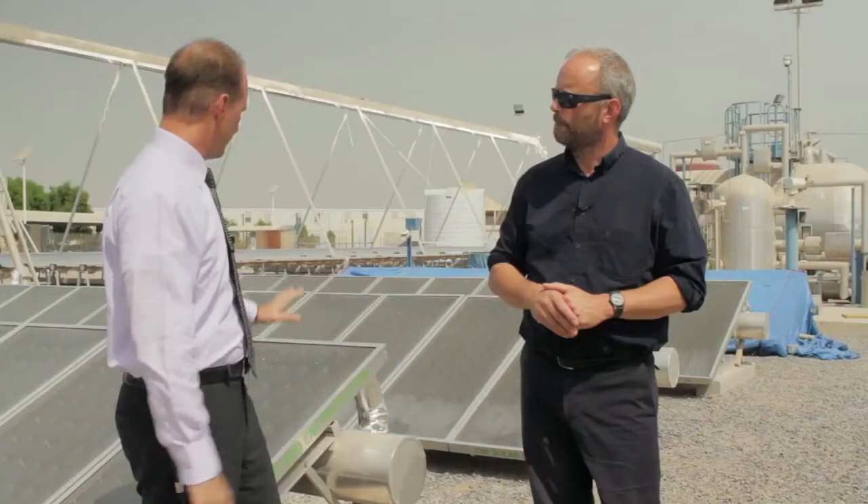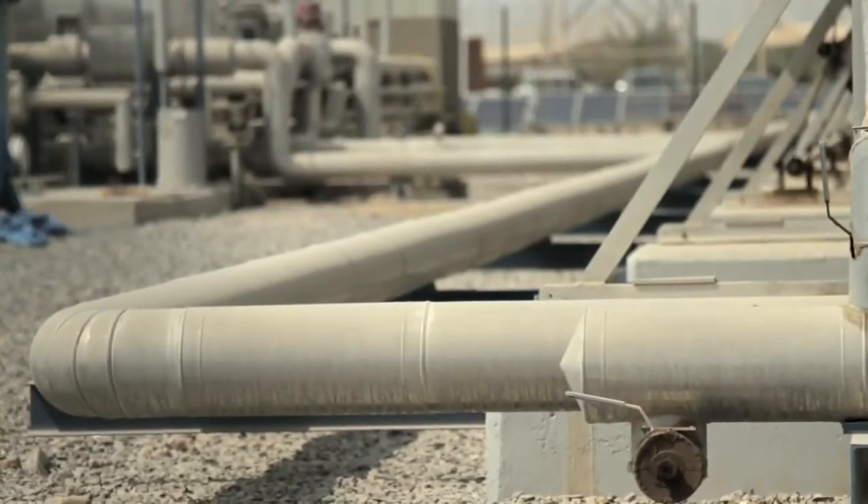That retains the thermal energy and then you can apply it to different purposes, so you could run a generator from it. Right here on this side we're actually making cooled water from thermal energy. Back here we have a big absorption chiller, which is a big refrigerator. We take the heat to drive that cycle and it cools water down, which is sent into the buildings behind us and cools the offices. And then behind us here is another slightly different system - another way to generate the heat. There are cost benefits in each system: a very high temperature but more costly system here, and a lower cost system that's easier to install. This heats water directly by using vacuum panels, and the vacuum insulates so you capture all the thermal energy and generate about 180 degrees Celsius water, kept under pressure to retain the heat, then driving the refrigeration cycle. These are two different ways we're benchmarking against each other to create cooling.